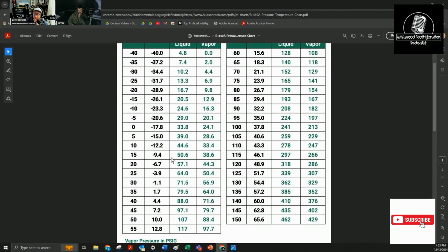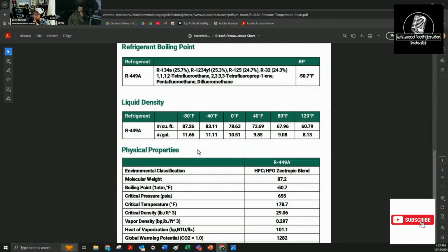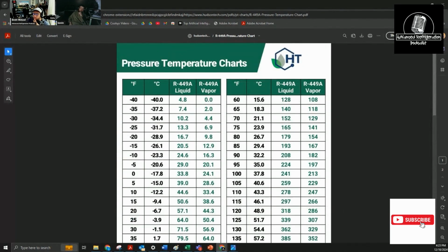When I do pressure controls, I try to do it with what the midpoint is, because you're getting a little bit cooler, a little bit warmer. I don't like doing that, just for the simple fact that as I've been programming more and more stuff, it throws off the superheat calculation in the suction groups. If you do it off midpoint, the superheat calculation is usually 4 or 5 degrees off, so it confuses people. I usually just end up raising the suction set point up enough to account for the glide.